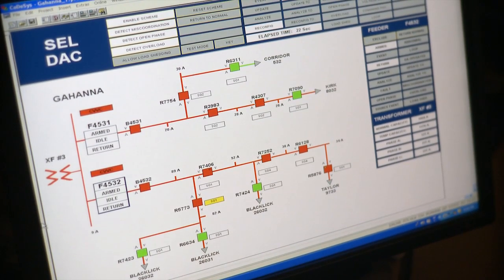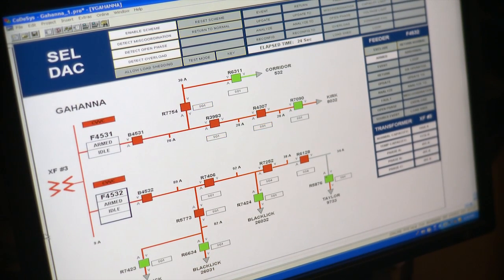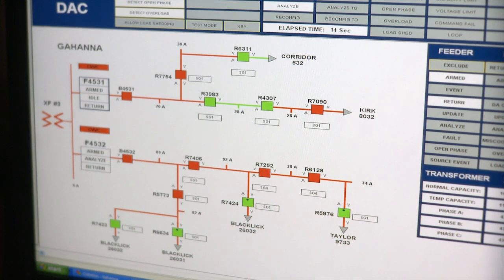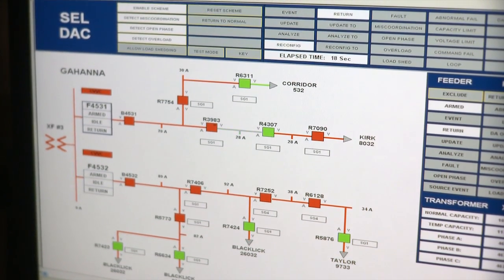The system will also respond to sequential events. If the DAC is in a current state of reconfiguration, it will reanalyze a new event and assess the whole system with multiple events in place. If the system has already reconfigured and a new event is detected, it will properly reconfigure the system based upon the new event and the existing configuration.